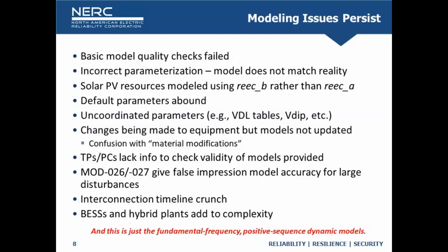They give a false impression that the model is entirely accurate, particularly for large disturbances. MOD 26 and 27 verify a number of parameter values you can count on less than one hand, but these models have well over 120 parameters associated with them. We can't make the false assumption that verifying four or five parameter values means I have a verified model. It means I've verified four or five parameter values—the other 125 have not been verified. We've given the false impression that if I receive a MOD 26 test report, that model's good. That's not true. In many cases we've had to fight that battle to say that model is actually bad, because the tests performed don't capture things like momentary cessation or large disturbance behavior.